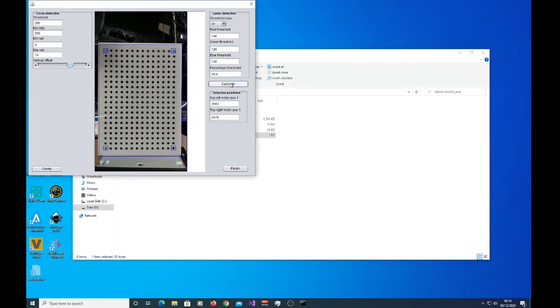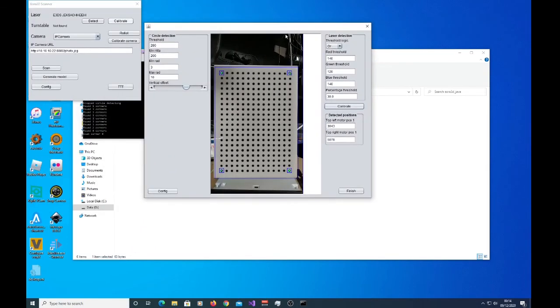Calibrate. There we go. So it waited, found all green dots. Now it's doing its 5-step fast search. And again, you can see what's going on here, where it's looking for the laser to intersect with the first corner. Now these motor positions are effectively what we're looking for. The motor position on the turret when it's hitting the left hand side of the top left black dot, and the left hand side of the top right black dot.